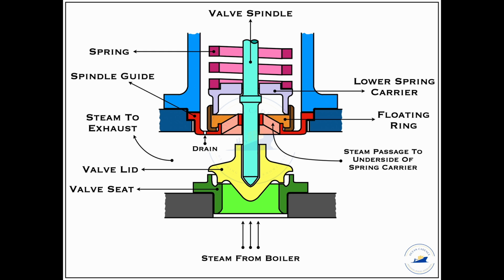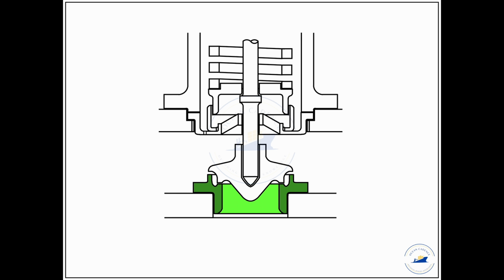Other general checks are to be carried out on the valve seat of the safety valve, and there can be manual grinding or lapping that can be carried out on these valve seats. However, before carrying out any such action, it has to be made sure that the diameter of the seat and the thickness of the surface are well within the prescribed limits of the manufacturer. For that, the safety valve assembly manufacturer's manual has to be referred to specifically. Only then the action of lapping has to be carried out.